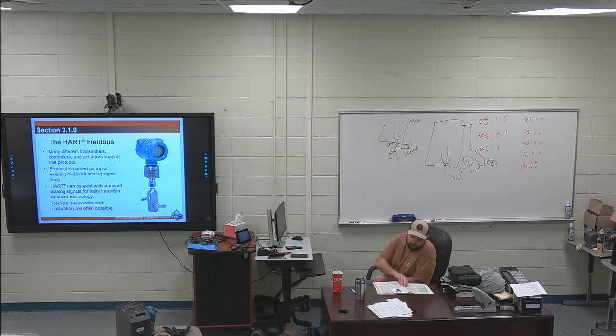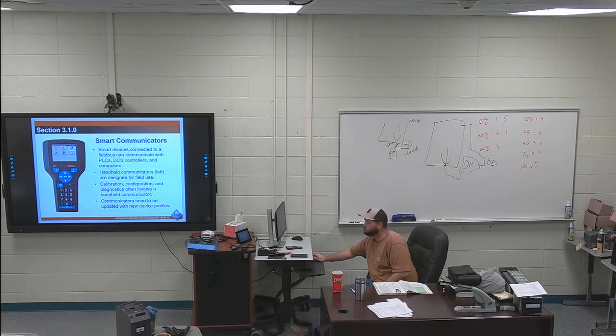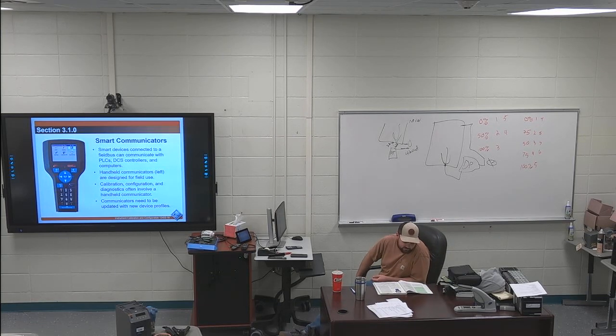HART protocol 310, what I was just talking about. The third paragraph, first sentence is highlighted. The HART protocol provides a two-way digital communications compatible with the industry standard 4 to 20 milliamp analog signaling, analog, used by traditional instrumentation equipment. You should know, a 4 to 20 milliamp signal is analog or digital? Analog, because it can go from 4 to 20.